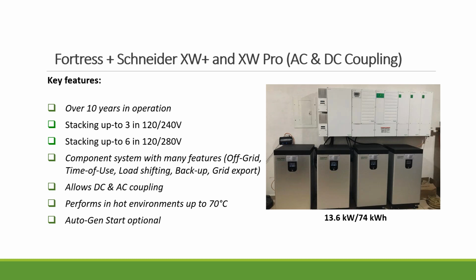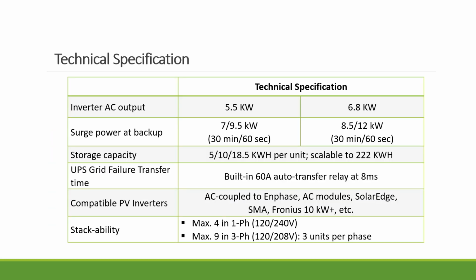You can do AC or DC coupled. If you want to do AC coupling, you just use the inverter. If you want to do DC coupled, then you get the charge controller. So it's flexible that way. It survives and actually works well in very harsh conditions, like a hot environment of 70 degrees. So for some off-grid applications, that's very important. You can also get a generator as an option. Here is some technical information.